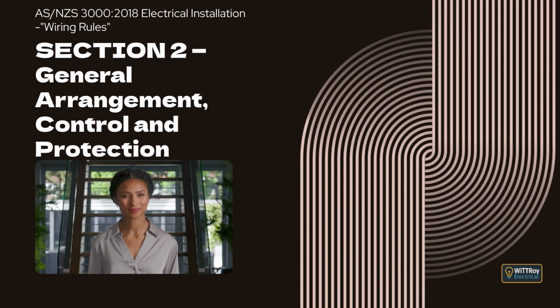There is one exception for non-domestic electrical installations. In some commercial or industrial sites, live parts can be exposed, but only when access is restricted to authorized and trained people, and when the area can be locked or controlled so the public cannot get near it. If removing a cover or panel will expose live parts, then that cover must be clearly marked so anyone opening it understands the danger. This marking follows the requirements of AS/NZS 61439.1. Domestic switchboards do not require this marking.